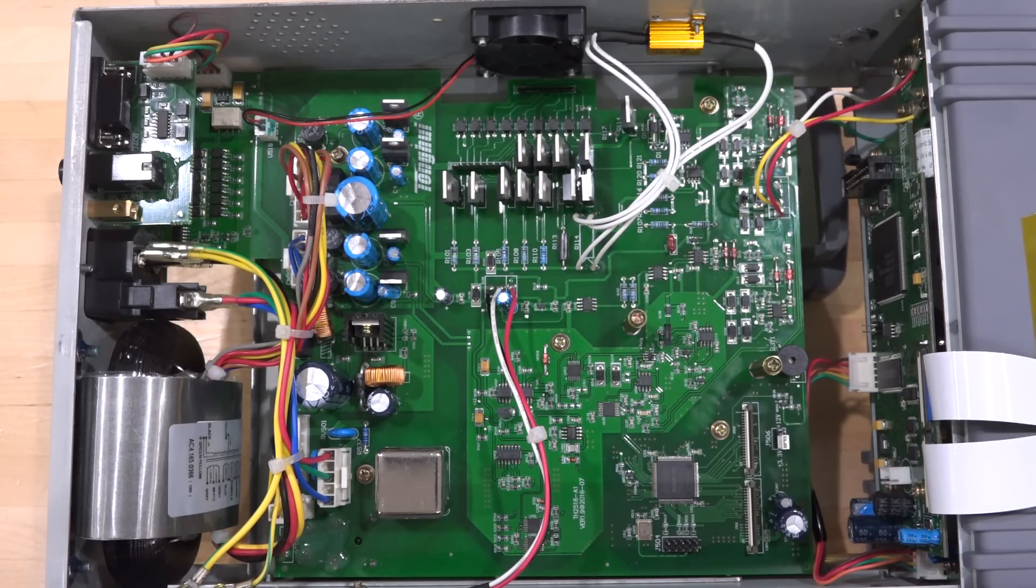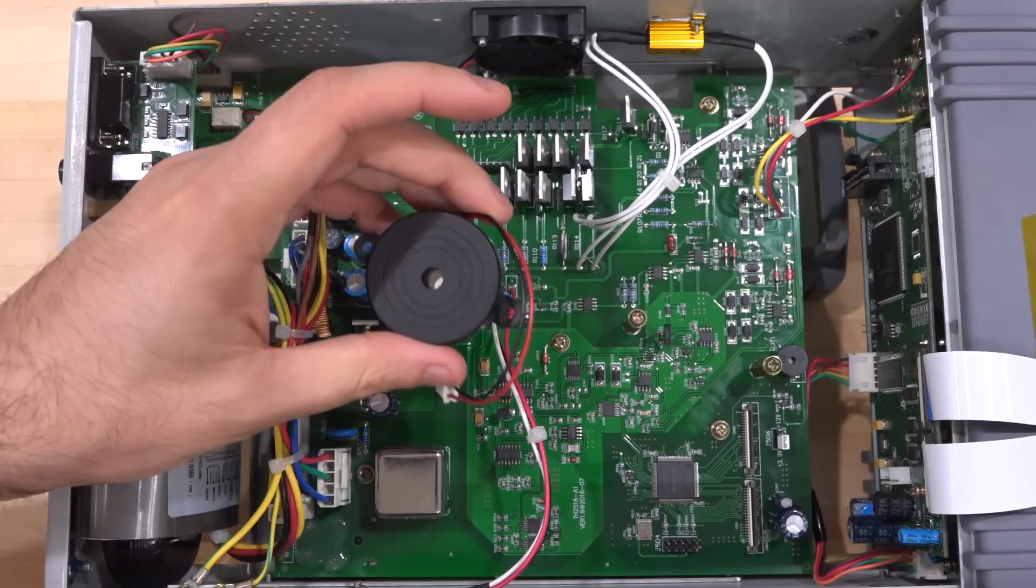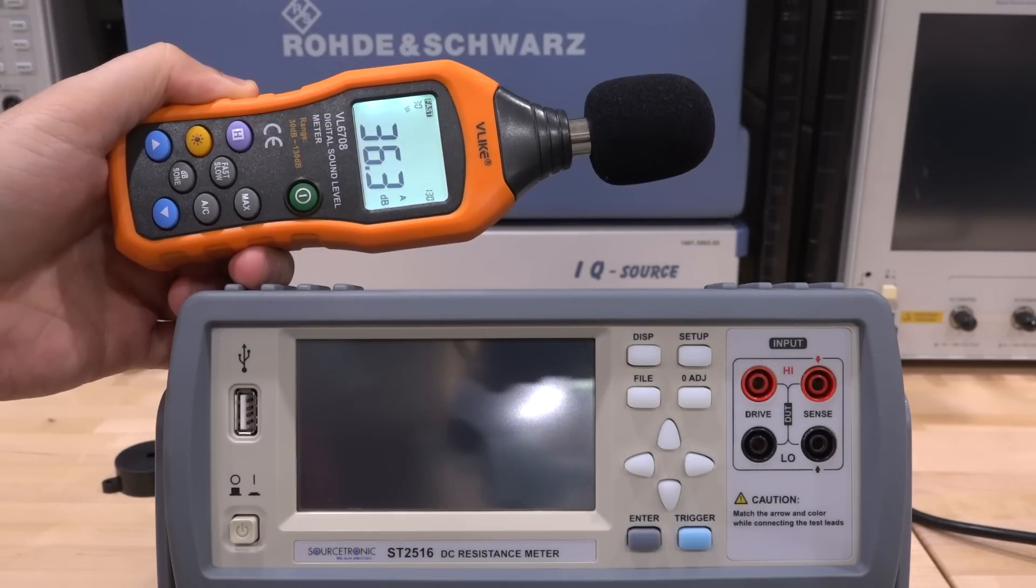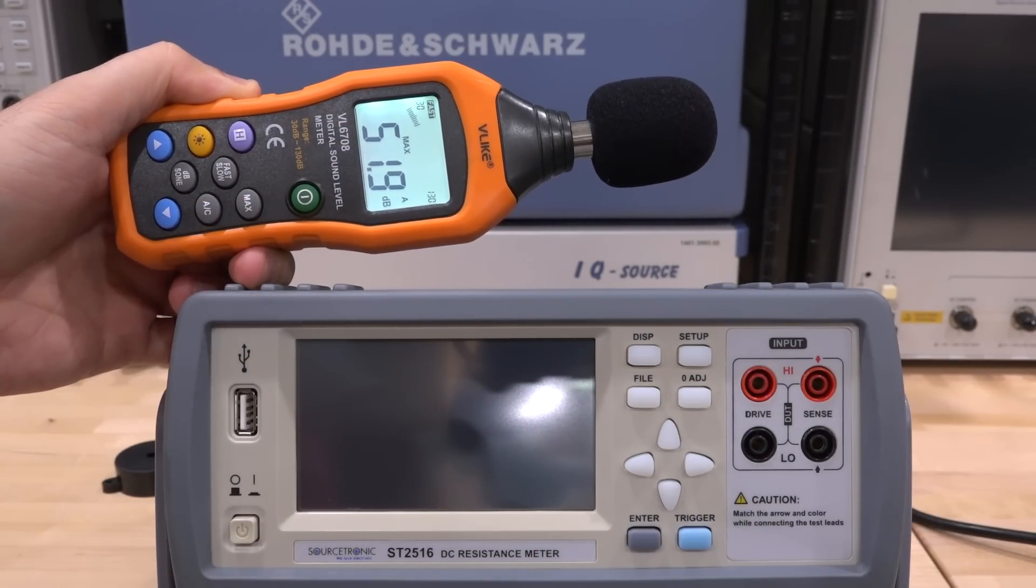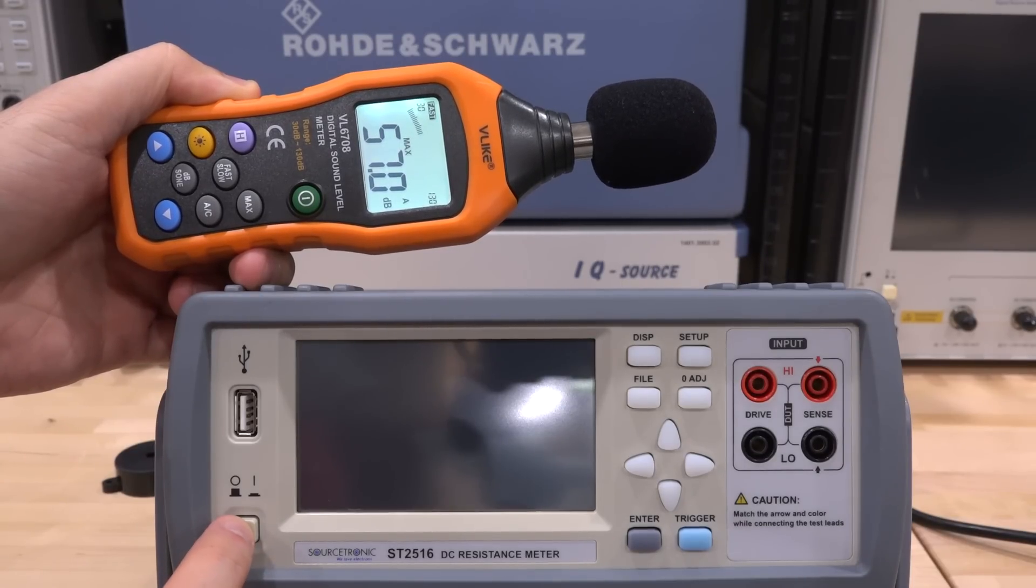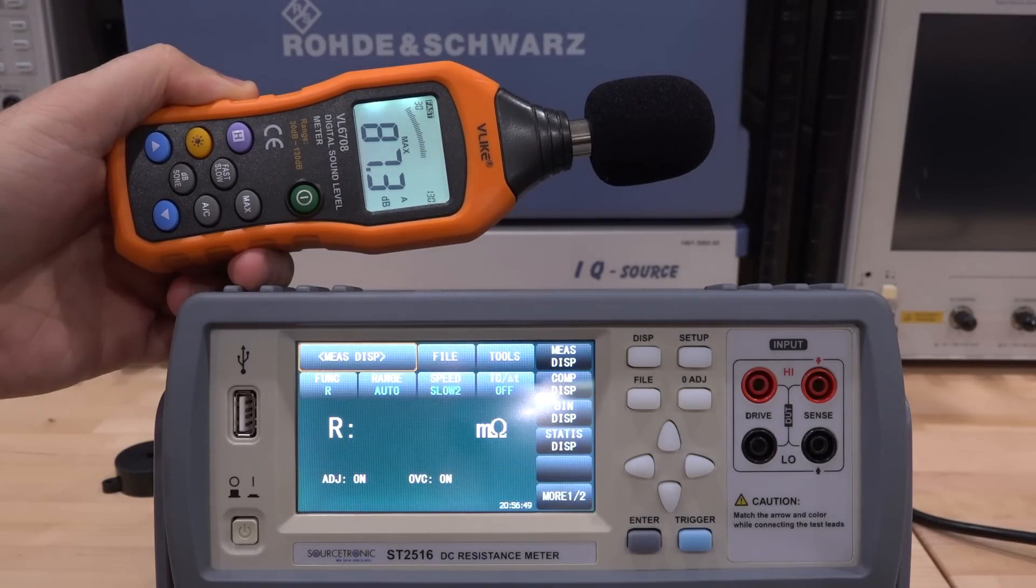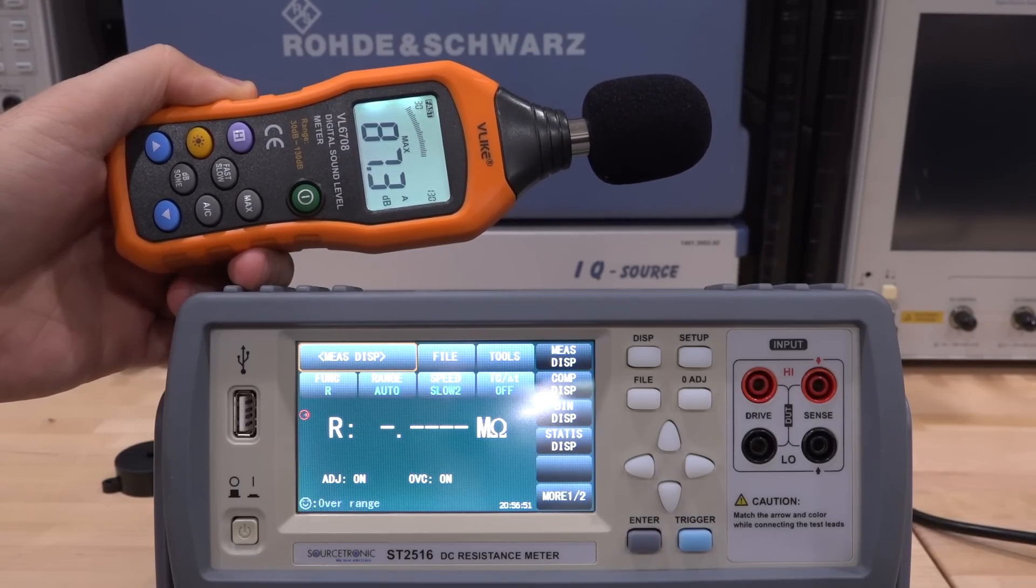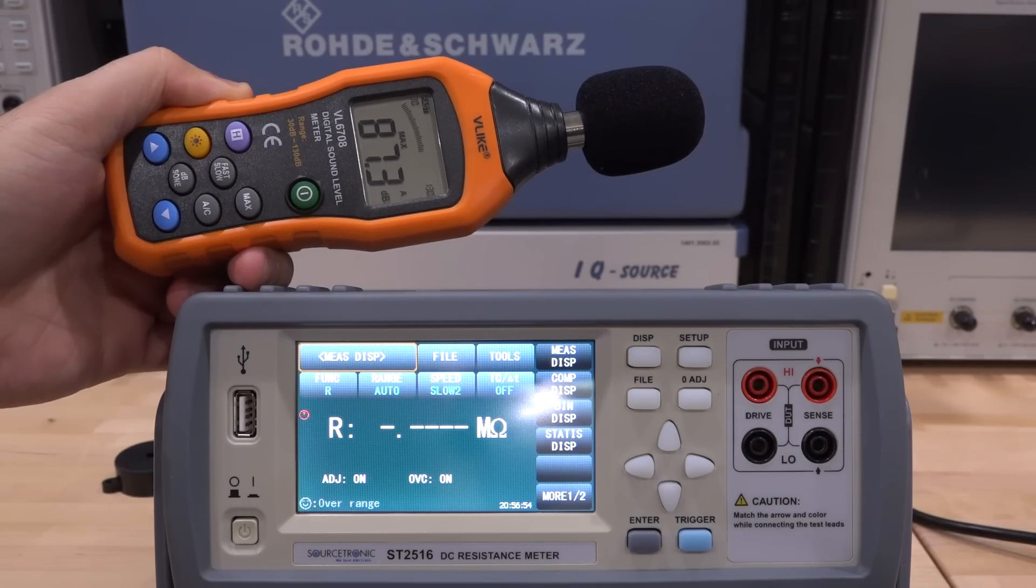Other than that it's really a straightforward device so let's turn it on and see how loud it is. I cannot show you the old one anymore because I removed it but at least we know that used to measure 110 dB. I'm going to put this on max hold so it just keeps the loudest noise it comes across. Let's turn it on. There you go, 87 dB, still pretty loud, the back of the unit is open but it is significantly more quiet than what used to be there.